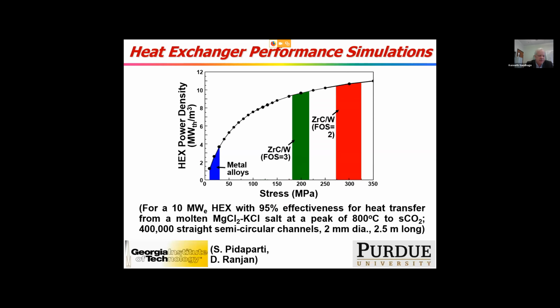Because the ZrC tungsten has a much higher failure strength, that allows you to make the plates much thinner for the stresses that are applied, say, with high-pressure supercritical CO2 in a heat exchanger. This is an initial calculation done for us by Sandeep Pitapparti and Devesh Ranjan, Professor Ranjan at Georgia Tech. Ashay's group has been continuing to do some of these types of calculations for us with modified geometries. Because the metal alloys do not have as high a failure strength, the plates need to be made thicker, which means that the power density, the megawatts of heat per cubic meter, is much lower.